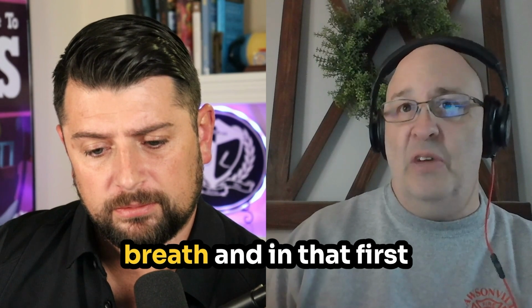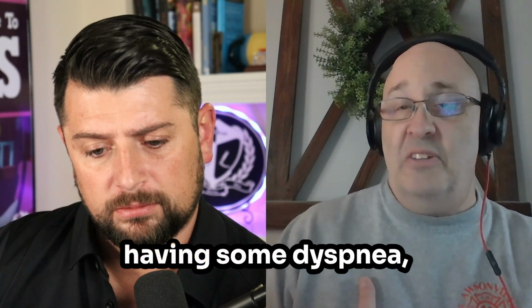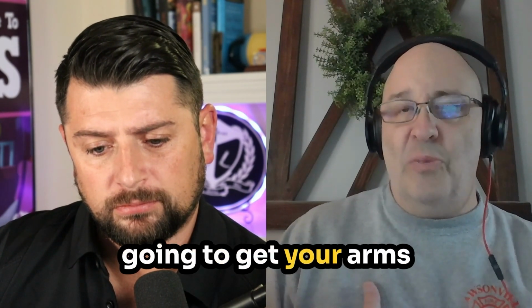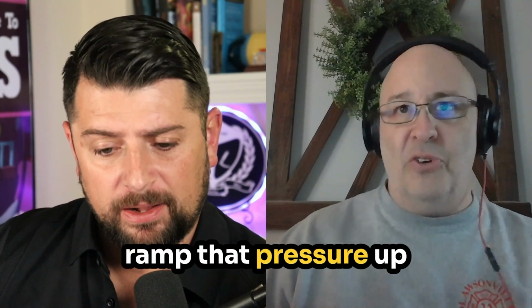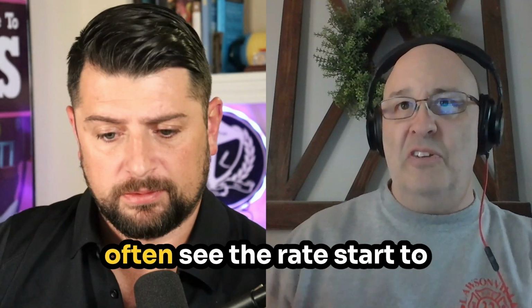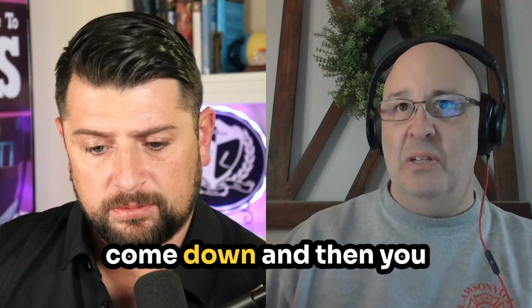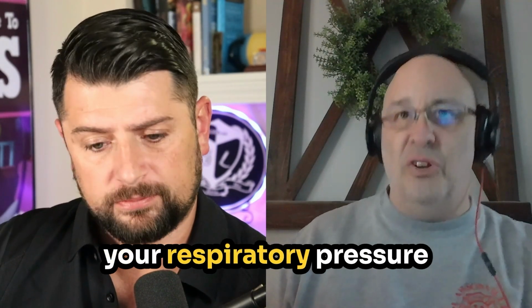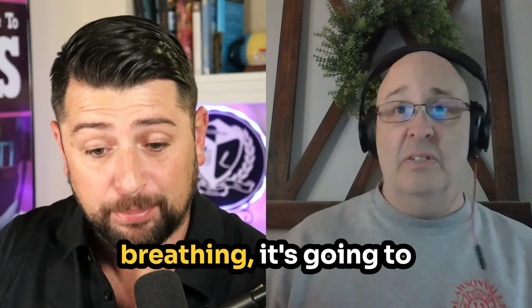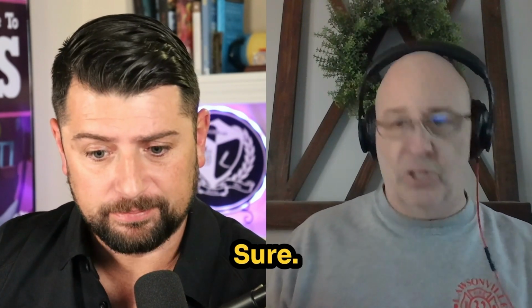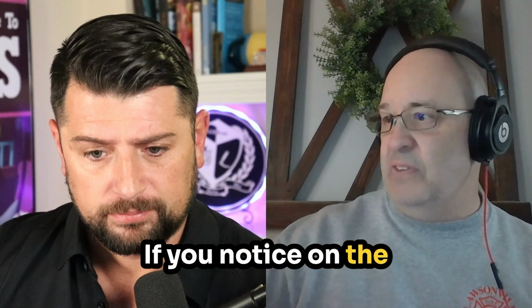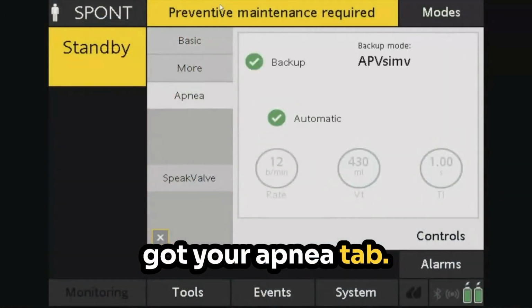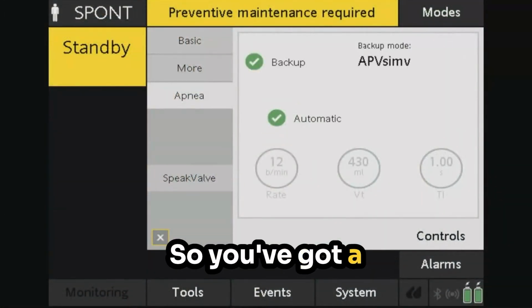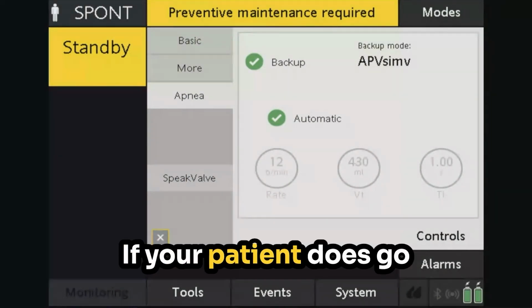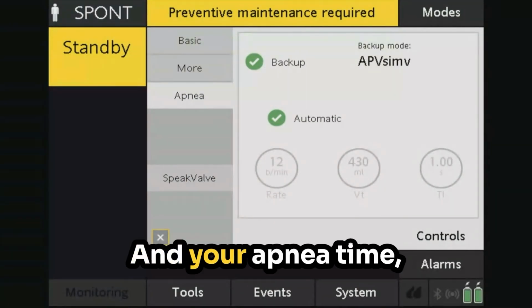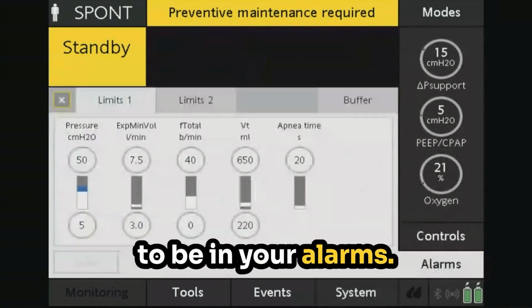If someone takes a breath and in that first few milliseconds they feel like they're having some dyspnea, you're never going to get your arms around it. But if you can ramp that pressure up and give it a big push on the front side, you'll often see the rate start to come down. And then you can start slowly titrating your respiratory pressure down. And if they stop breathing, it's going to kick over into PCV, right? Yeah, sure. It's going to kick over into apnea. If you notice on the left-hand side, you've got your apnea tab. So you've got a control set in place if your patient does go apneic. So you're covered. And your apnea time, by the way, is going to be in your alarms, 20 seconds.